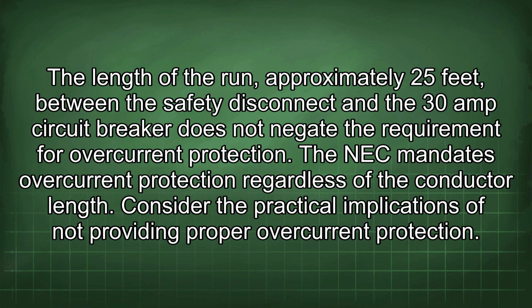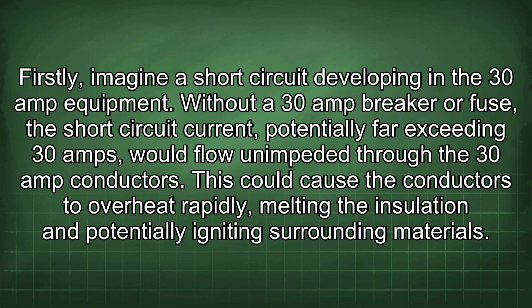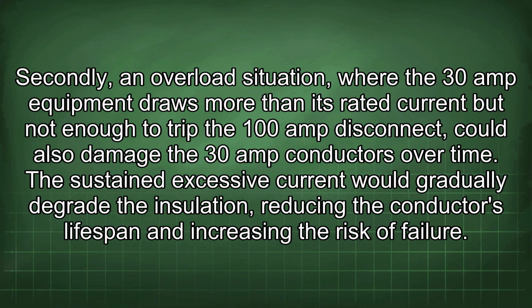Consider the practical implications of not providing proper overcurrent protection. Firstly, imagine a short circuit developing in the 30 amp equipment. Without a 30 amp breaker or fuse, the short circuit current, potentially far exceeding 30 amps, would flow unimpeded through the 30 amp conductors. This could cause the conductors to overheat rapidly, melting the insulation and potentially igniting surrounding materials. Secondly, an overload situation, where the 30 amp equipment draws more than its rated current but not enough to trip the 100 amp disconnect, could also damage the 30 amp conductors over time. The sustained excessive current would gradually degrade the insulation, reducing the conductor's lifespan and increasing the risk of failure.